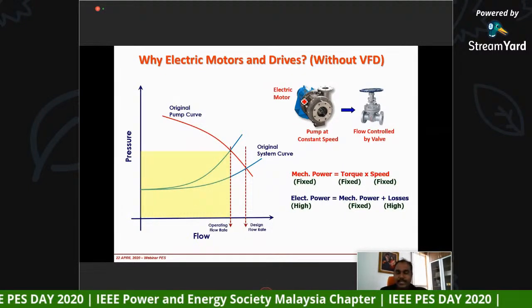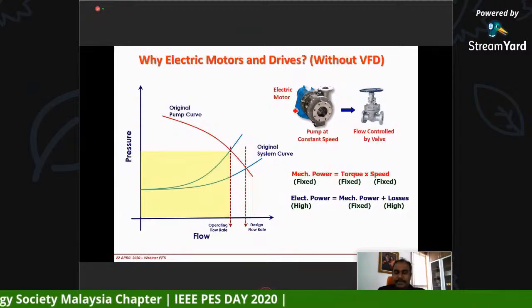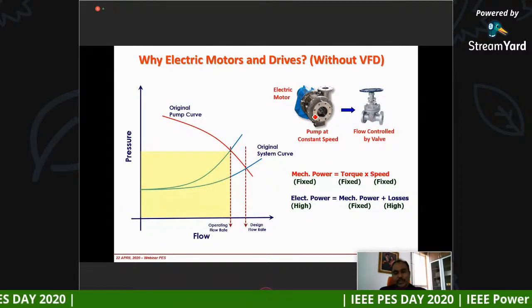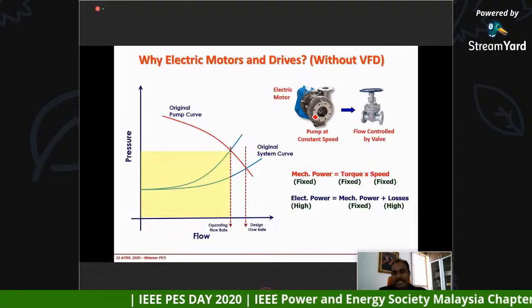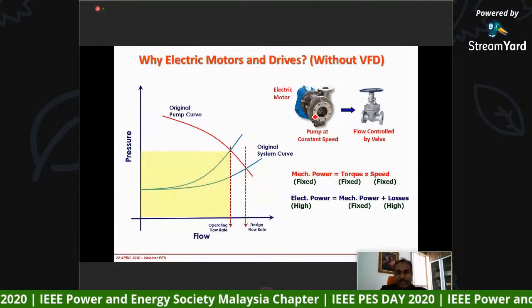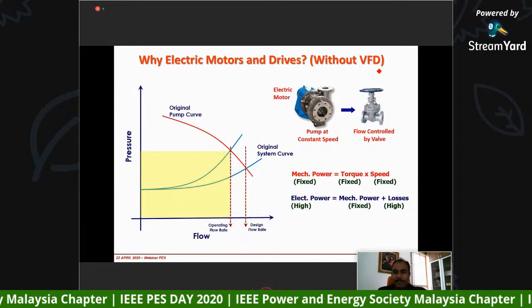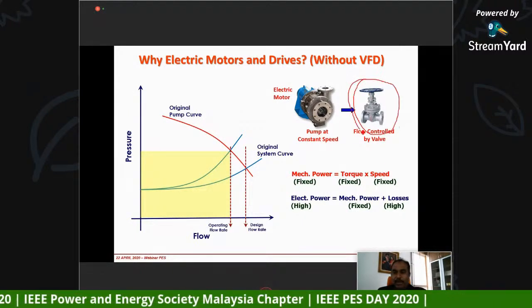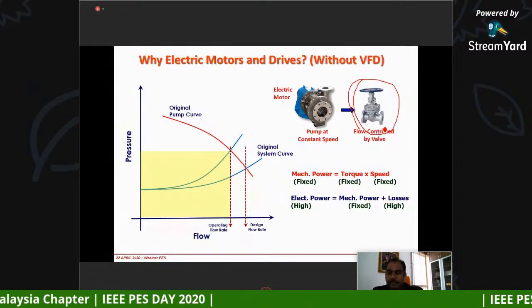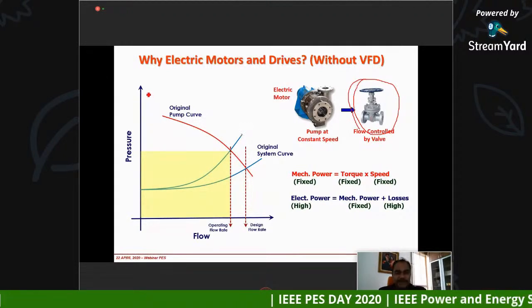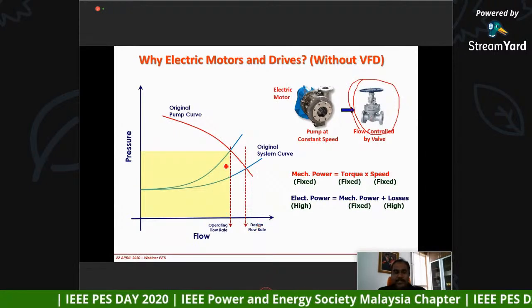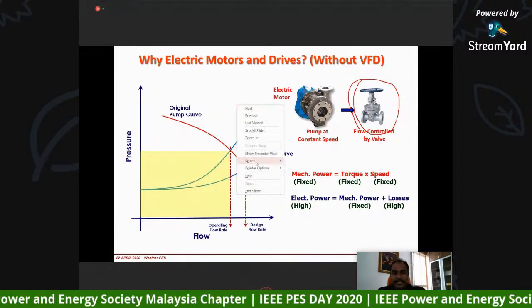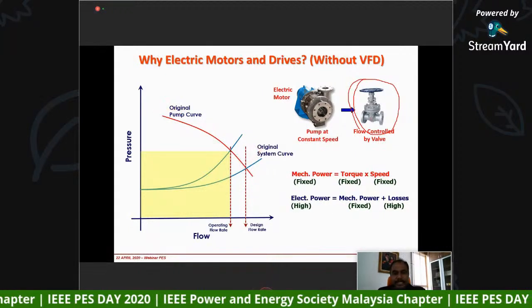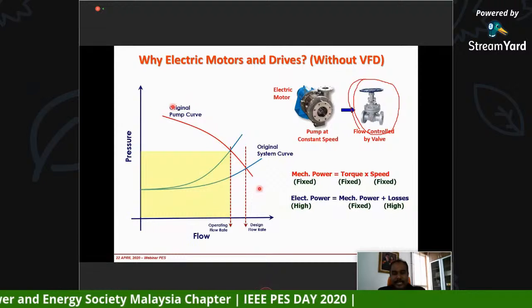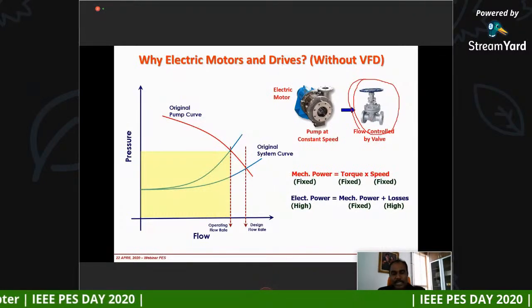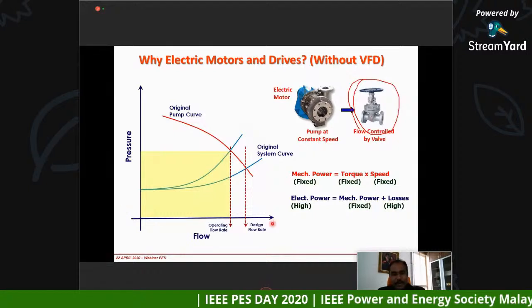Now, very quickly, let me go through this pump system. Pump systems are usually used to transport a liquid, for example water, from one place to another. Usually the pipe system will have a mechanical valve to control the flow. When you look at the curve here, this is the pressure versus the flow. The red line here is the pump curve. When you are selecting a pump, the pump manufacturer will give you this curve, pressure versus flow, and this is the pump curve.